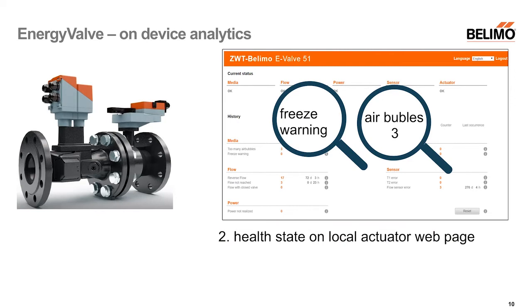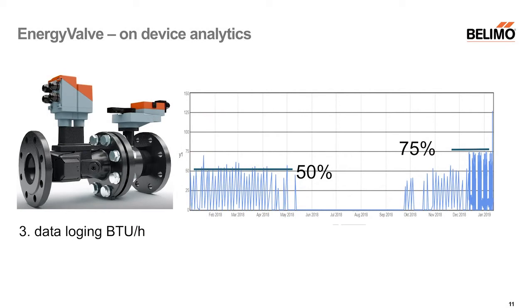There is a health state report on the webpage directly coming from the product. For example, it can tell you there is a freeze warning, or that air bubbles were detected — things the product itself can detect to help ensure your system is safe. Then there is the data log: 13 months of data showing the power going to the heat exchanger. Looking at this number over a year, you can see it was never more than 75%, confirming safe operation even in a very hot summer — this is something you can read directly from this data.